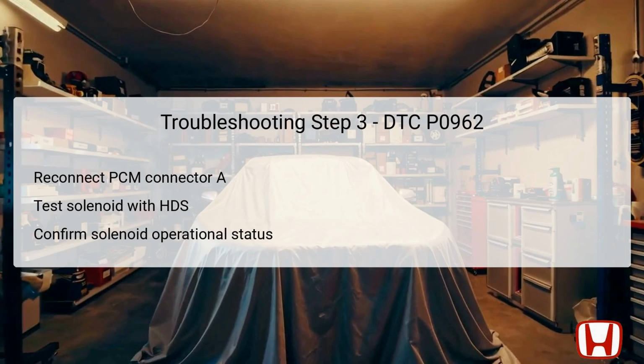During this operation, the HDS will provide real-time feedback on whether solenoid valve A operates within expected parameters. If the HDS indicates a normal status, it confirms functional integrity of the solenoid. Conversely, a failure indicates further issues may exist within the solenoid or its associated circuitry, directing the technician to proceed to the subsequent step.